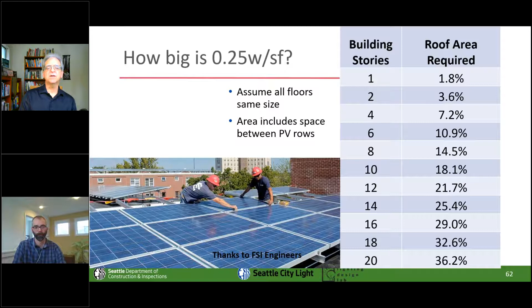I'll just note, on plans when you're getting into that sizing, a good rough rule of thumb is 1,000 watts of panels is going to take up about 100 square feet of roof. That's a really rough rule of thumb, but it's one that has stood the test of time even as modules are getting more efficient.